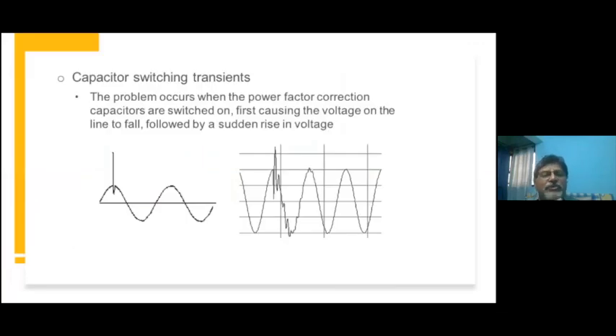And going to the next. When you use a capacitor, as I said just before, it can cause over voltages. These over voltages can happen both at the time of closing and opening of a capacitor. Especially if your capacitor is feeding a network or a load, it can happen if the capacitor is overcompensating the load. For example, it is quite possible in a factory that you come across a situation where you have a 25 kVAR 5 steps or a 50 kVAR 5 steps. Now, if your load demand is only, let's say, 10 kVAR, and your minimum step is 25 kVAR, what happens is the 25 kVAR will immediately try to switch off at a light load, and that can create a surge.